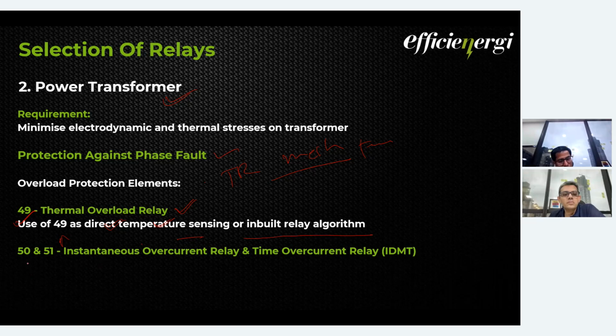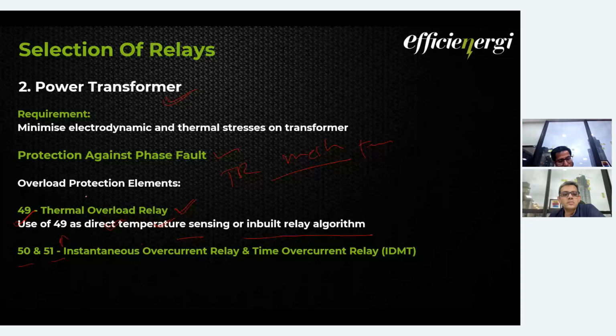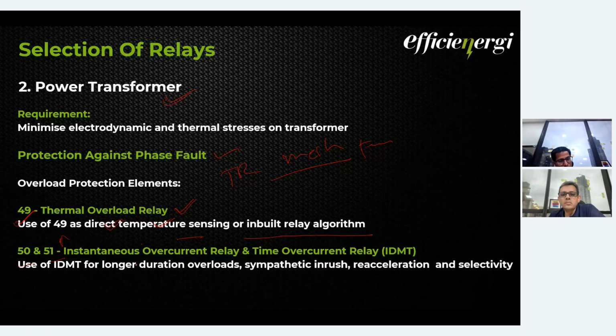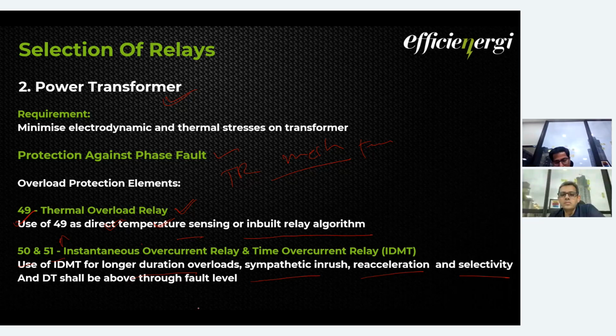Then again, a regular 50-51 you are using for transformers. Use IDMT for longer duration of overload, sympathetic inrush, reacceleration, and selectivity. We are using the IDMT zone. And for DT, we are keeping it for a fault which is above through fault level, that is a secondary fault.